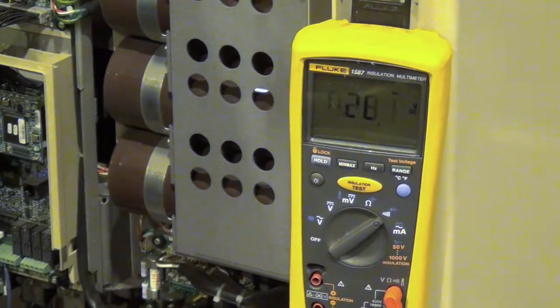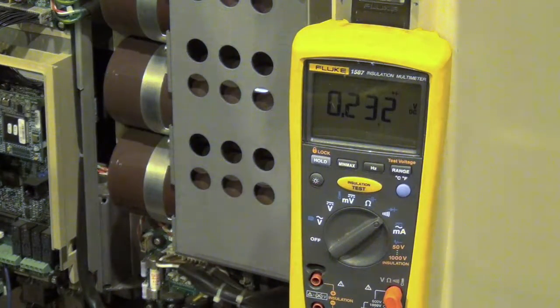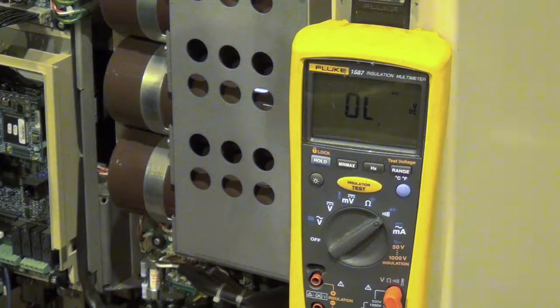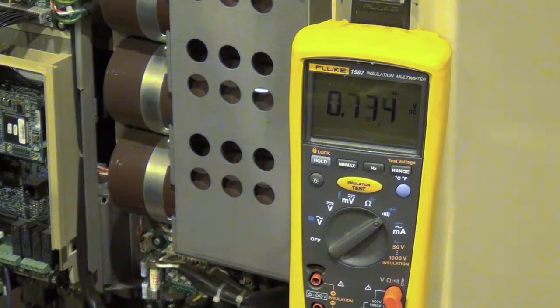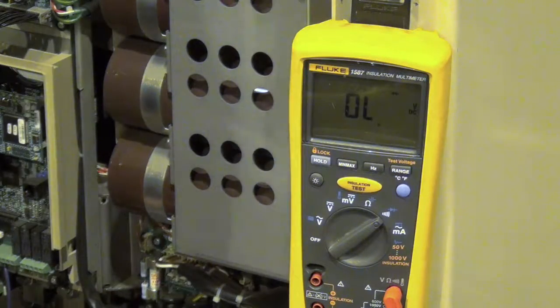We get a 0.23, 0.23, 0.23. We're going to switch our probes. Perform the same test. We get a value that's climbing. We're at 1, still at 1, still at 1. So again, that side shows normal. So now I'm going to adjust my probes.